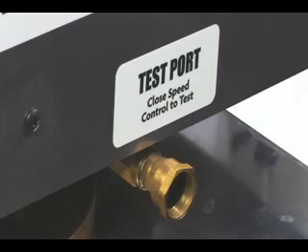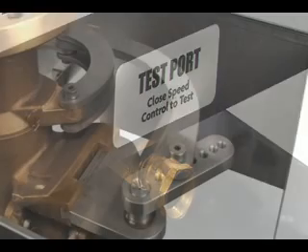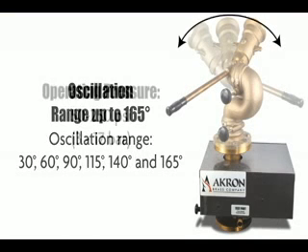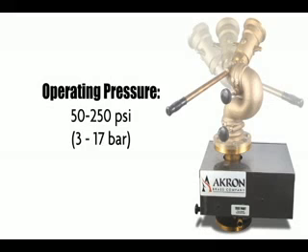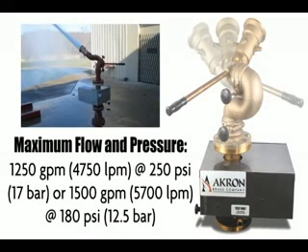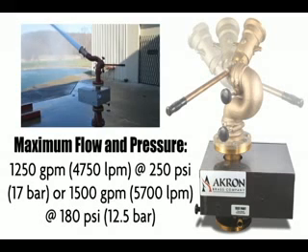of the oscillating flange without discharging water from the monitor. Easy access to oscillating range adjustment — Akron's oscillation range is up to 165 degrees.